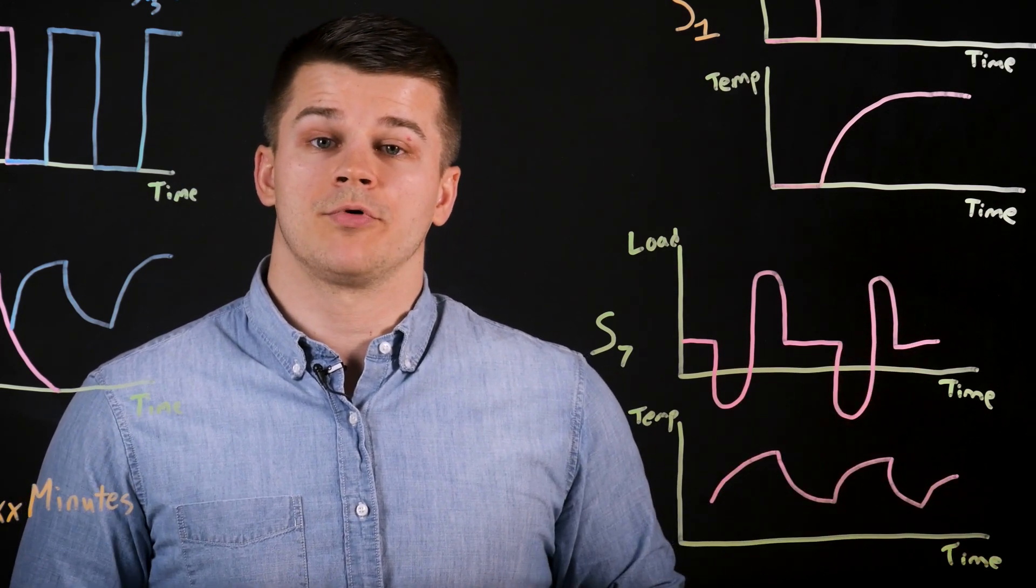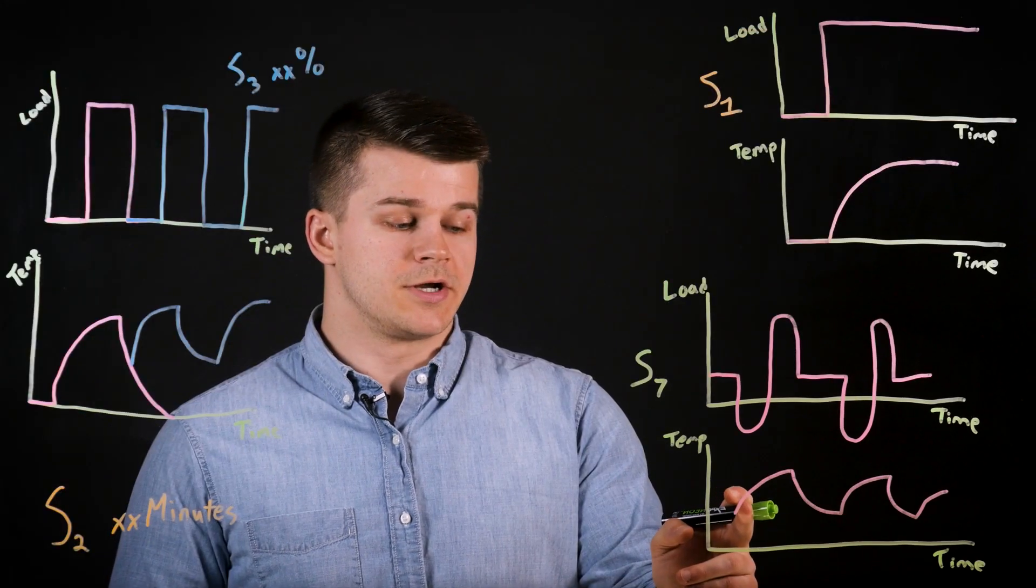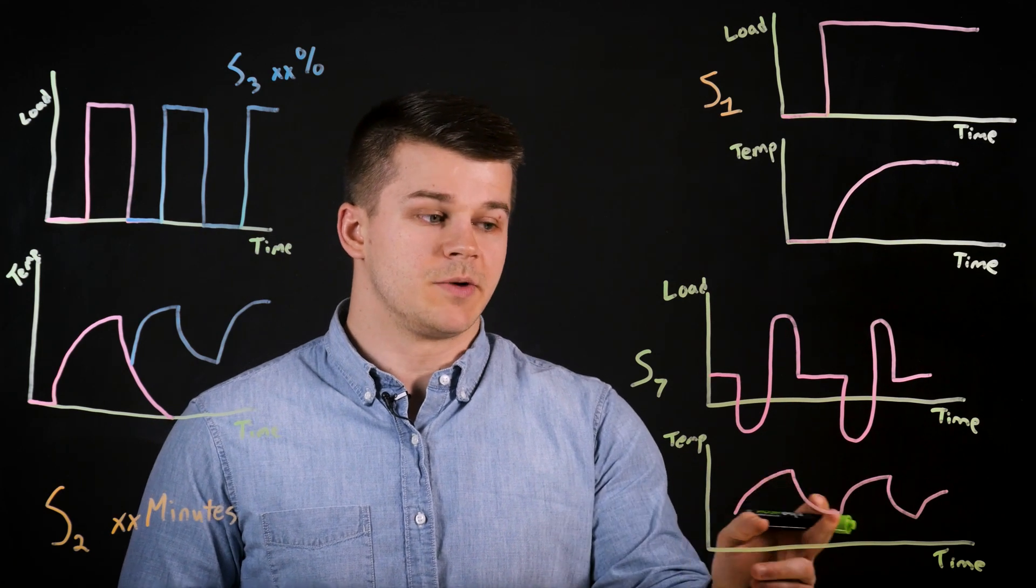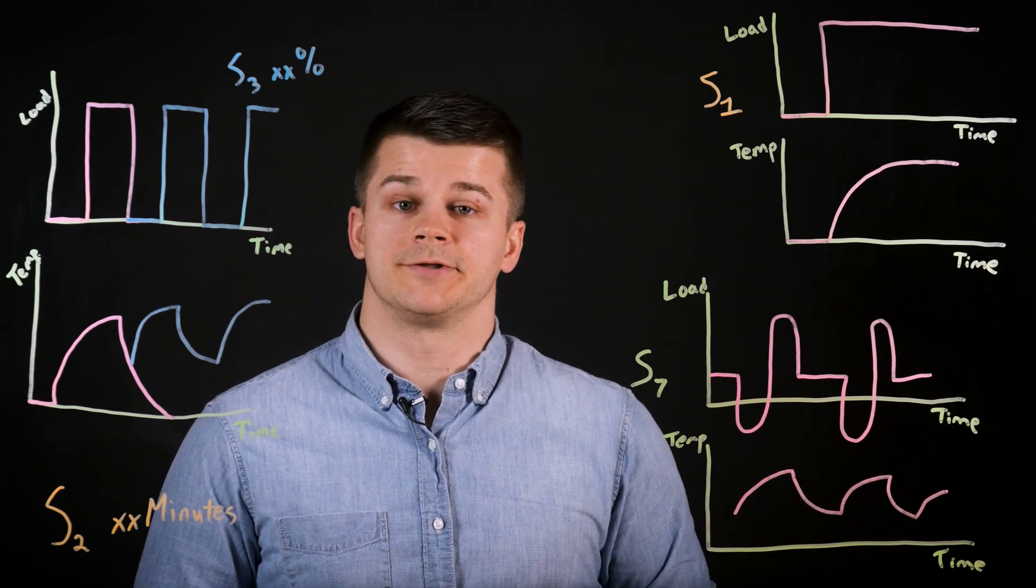During this type of operation, the motor does not get any rest periods. The temperature increases the most during the electric braking and starting portion, and it's allowed to somewhat cool down when the constant load is applied to the motor.